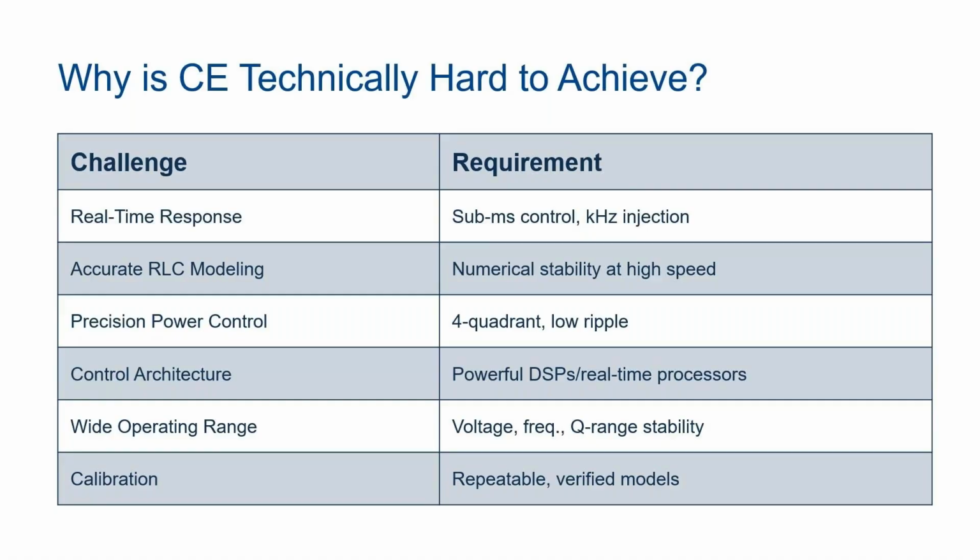It requires typically to do any power factor from +1 to -1 through 0. It needs 4-quadrant capability in order to do that. Low noise and ripple can be beneficial as well. And to do the real-time calculations to meet these load requirement simulations, you need very fast processing. So typically either gate array or DSP type, real-time processing of settings and feedback from voltage and current readbacks.